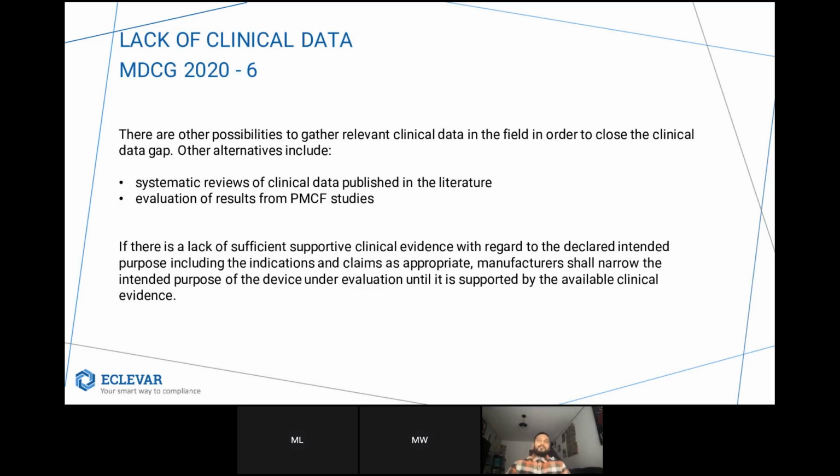Lack of clinical data. So this is a big question, I suppose, when it comes to CERs. There are issues where companies that I have worked with have had a lack of clinical data. Then you have to look at other aspects. Sometimes devices may be too new, or there could be just not enough data to support their claims. Again, you always come back to the claims and you need to support those claims. If there is a lack of sufficient supportive clinical evidence with regard to declared intended purposes, including the indications and claims as appropriate, manufacturers have to narrow down the intended purpose of the device under evaluation. So yeah, that's good to bear in mind.